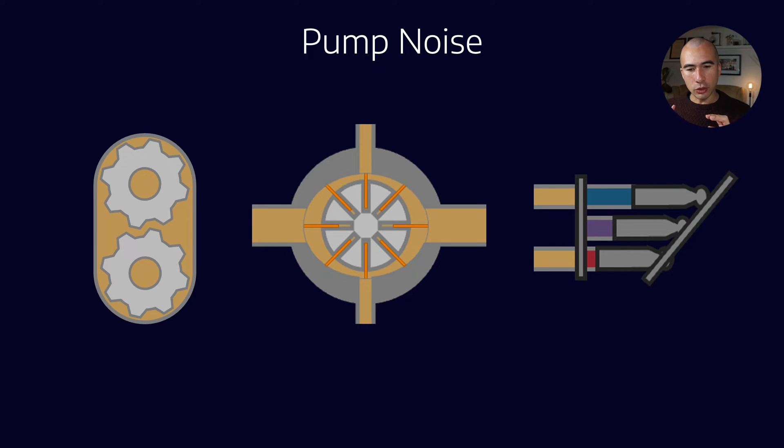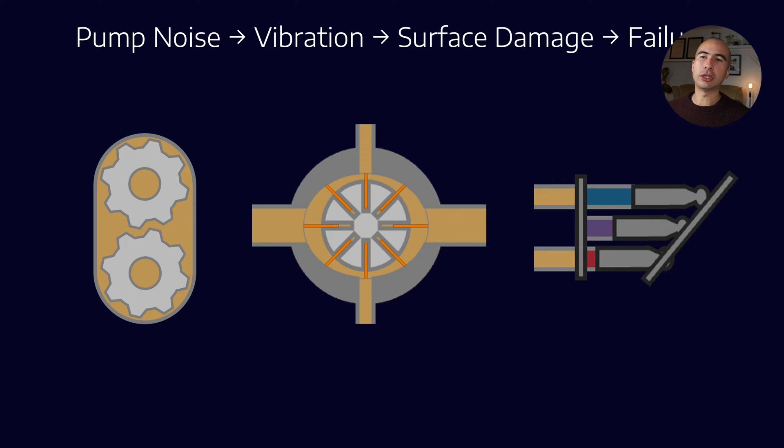Now when you have micro-dieseling, it usually is recognizable by some kind of pump noise. You'll hear noise coming out of a hydraulic pump that is very unusual. It sounds almost like someone is gargling marbles. It's a very clattering sound. And when you hear those pump noises, that can lead to vibration and then surface damage and ultimately failure of the system.